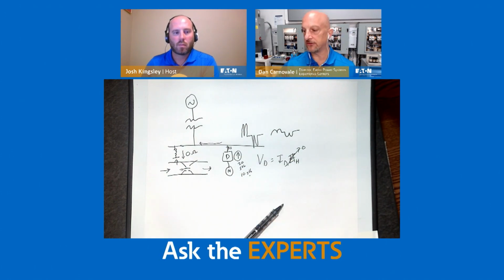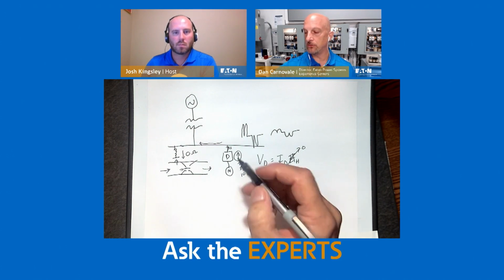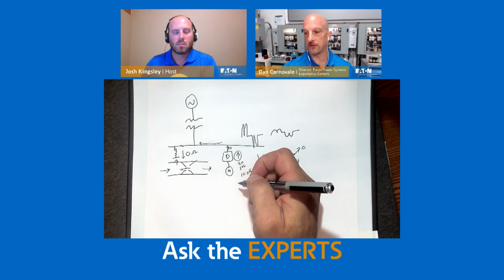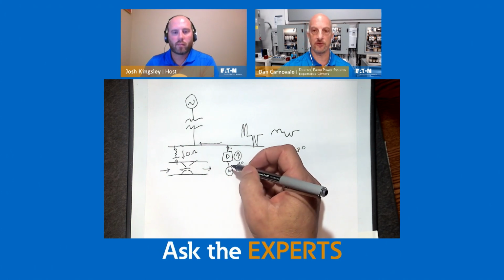The other thing is to select perhaps the right drive. We talk about 18 pulse clean power type drives, our medium voltage drives, perhaps 24 pulse to keep that limit down to a reasonable level. And then you go all the way up through broadband filters in front of the drives and active front ends and so forth. So there's a lot of different solutions.